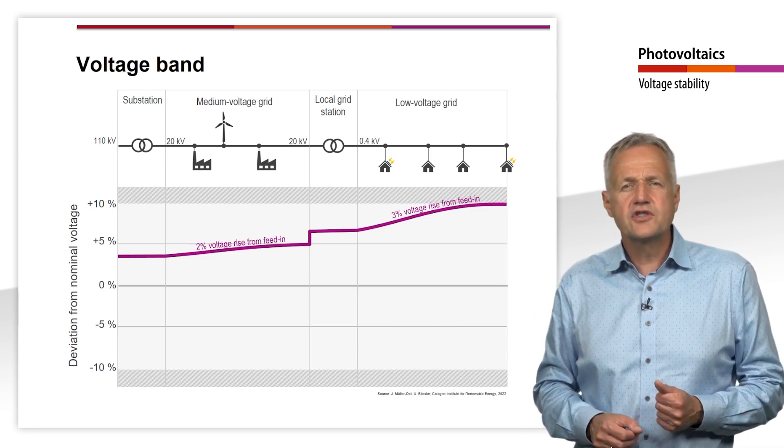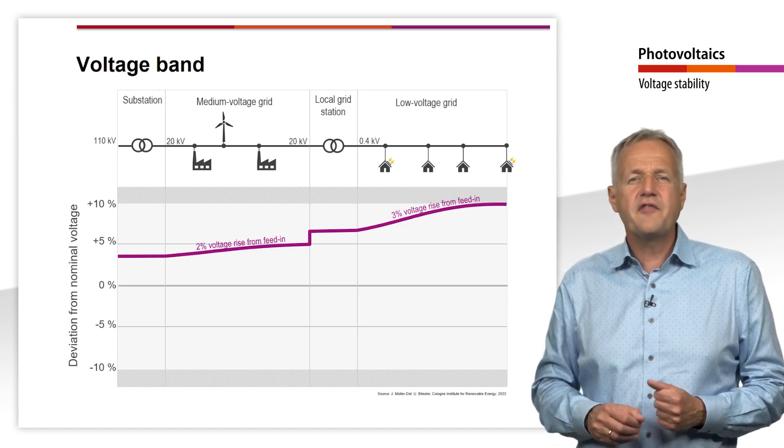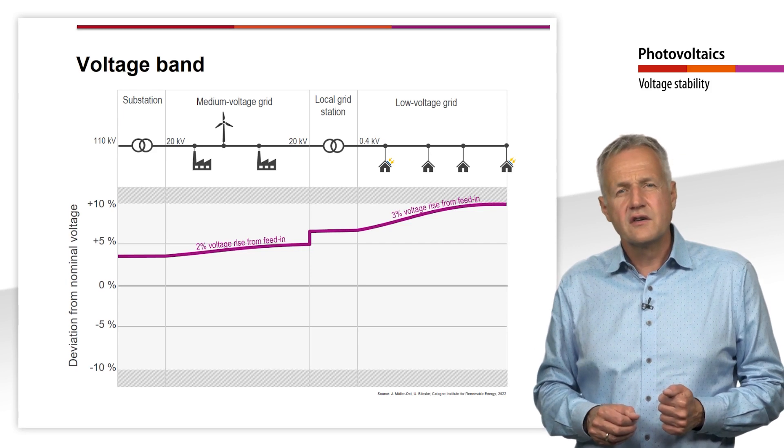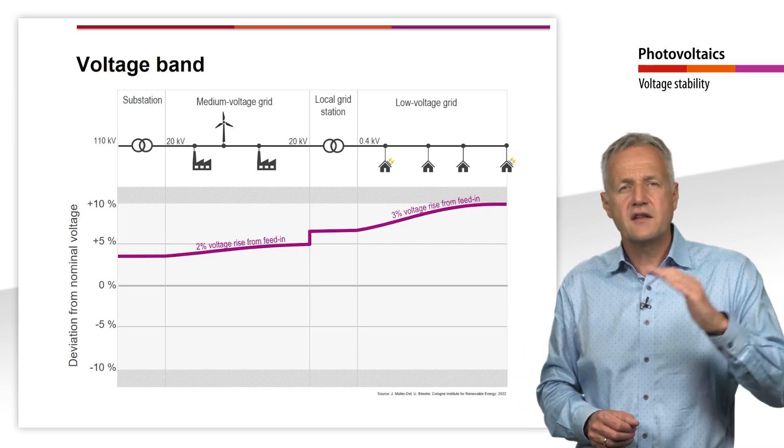The remaining distribution of the voltage band varies among the different grid operators. Typically, 5% each is allocated for the voltage drop in the medium voltage and the low voltage grid.